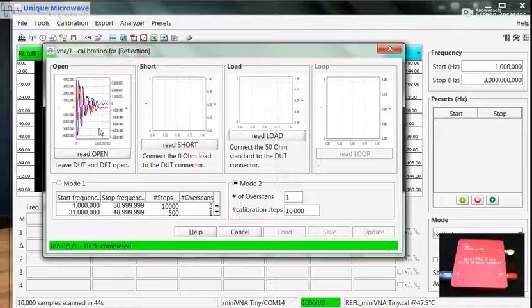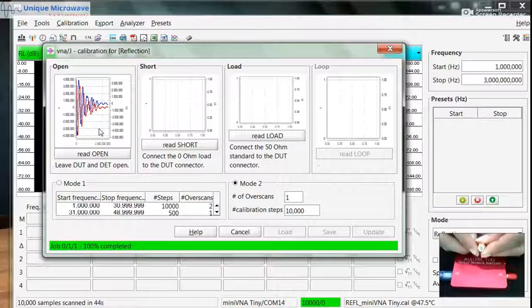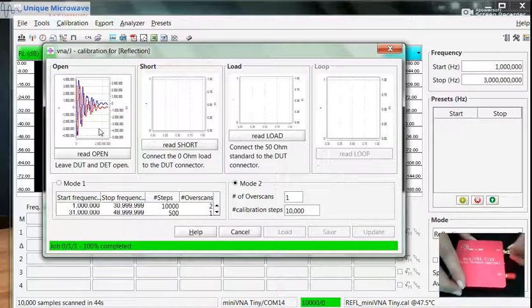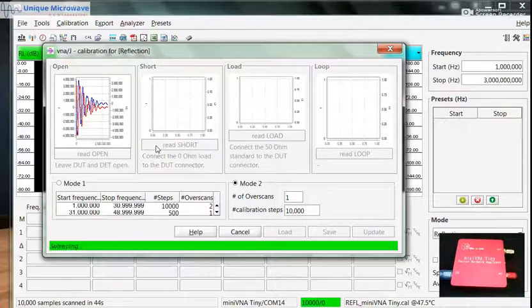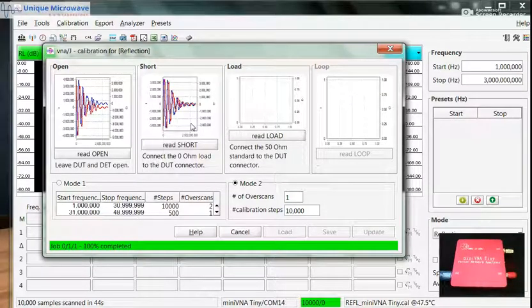This graph shows that the open calibration is completed. Now we can remove the open circuit and replace it with the short circuit kit. This is the short circuit kit. Connect it to the DUT port. Once it's connected tightly, click this to read Short. After a few seconds, the calibration of the short circuit is completed.